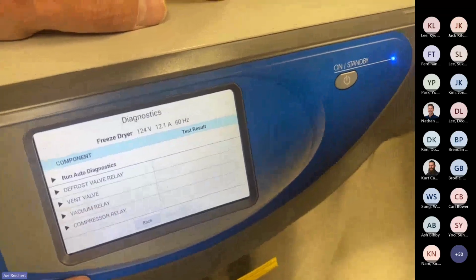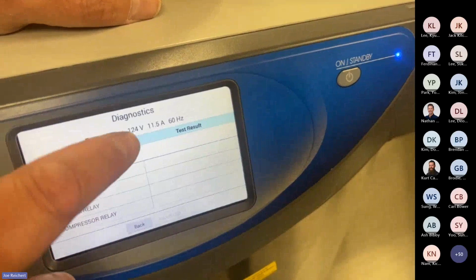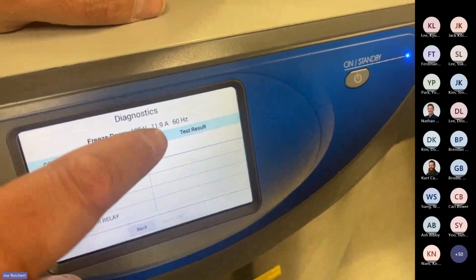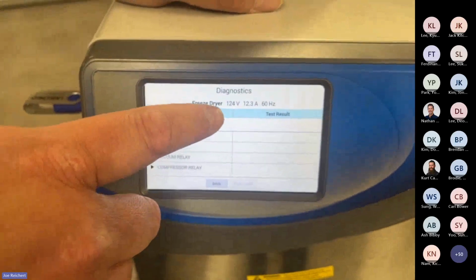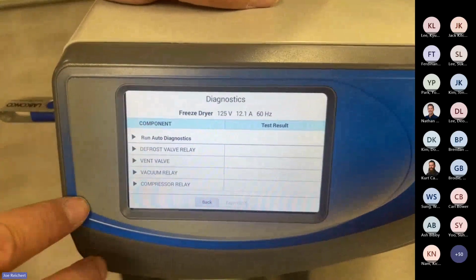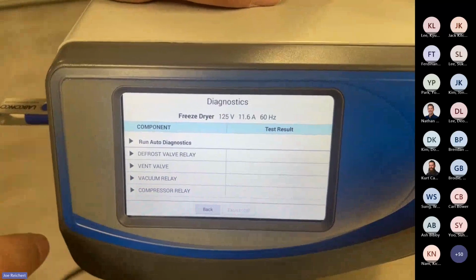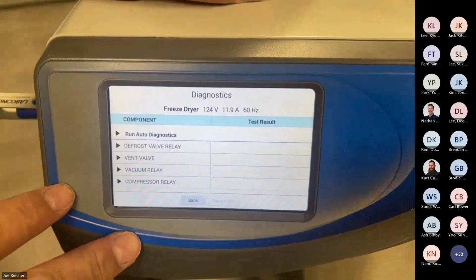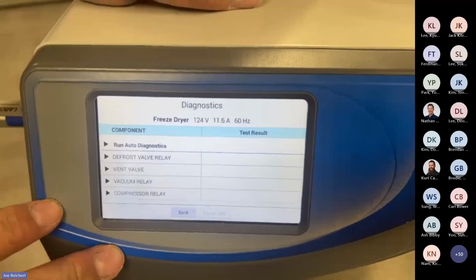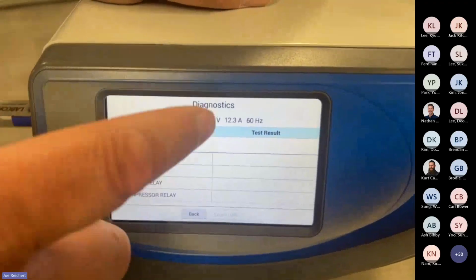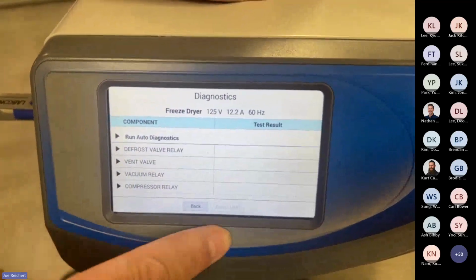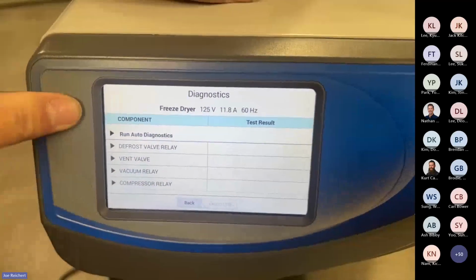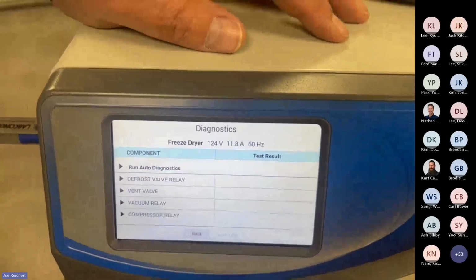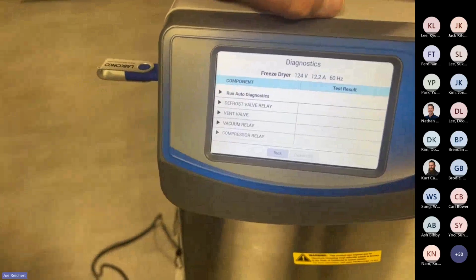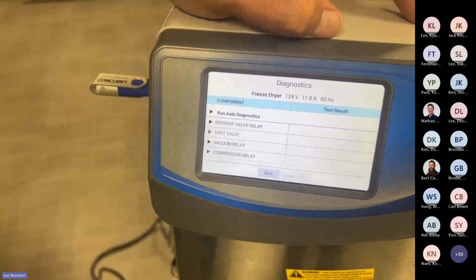The unit does have a power monitoring board, so it will tell you what your voltage is going to the units and how many amps are being drawn. This being a 2 compressor system and 115 volts, we run a higher amperage here in the US versus the 230 volt models, when you turn on your vacuum pump and everything's added in there together. You can also troubleshoot things like, is your vacuum pump maybe pulling too many amps, maybe popping the breaker on the back of the machine.